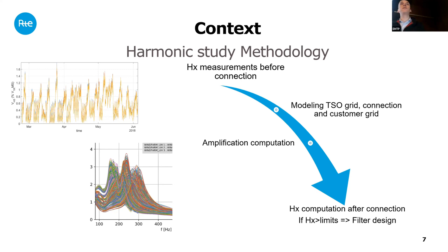The amplification factors are calculated with a simple method: a voltage divider that depends only on the different impedances represented here, namely the wind farm impedance, the cable impedance, and the onshore transmission grid impedance.